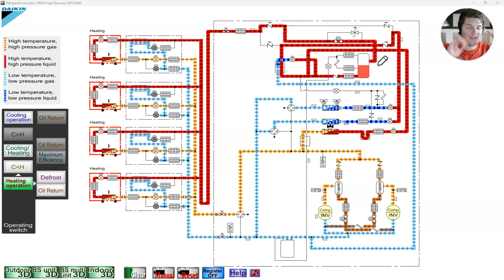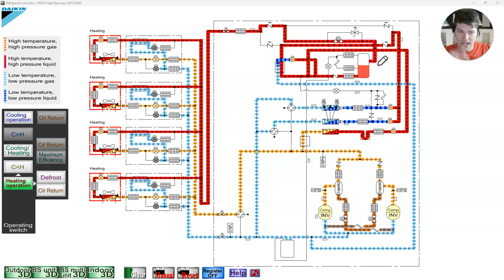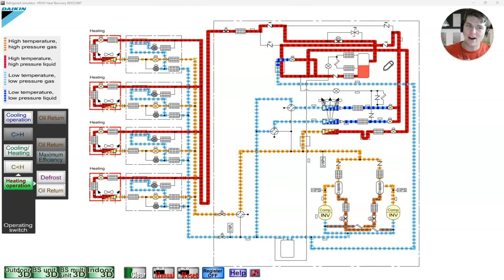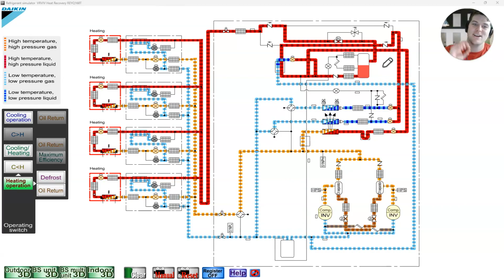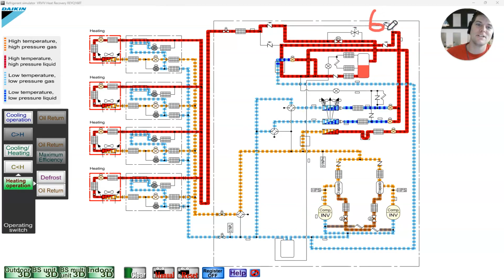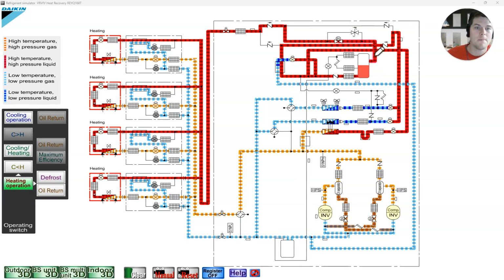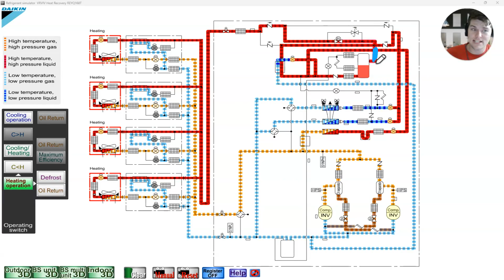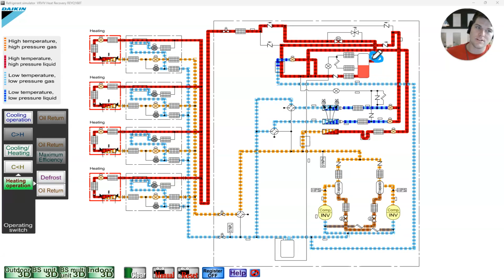And you're like, wait a minute, this is a liquid receiver. The animation shows liquid. Come on now. That doesn't make any sense. Let's peel back this onion. So I'm at 6.8 degrees at my liquid receiver right here. And I'm going to change this color just to get this point across to you. We're at 6.8 degrees here. We were at 20 degrees subcooling here at this point in the system. And now we're at 6.8 over a 95 degree saturation temperature.